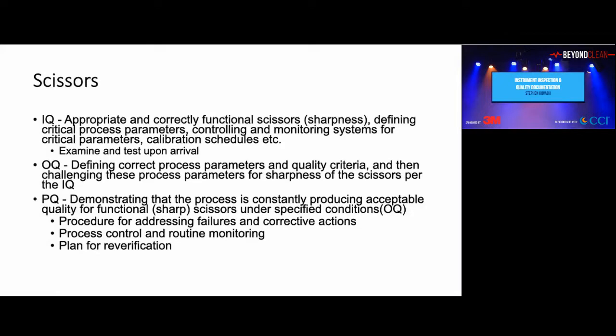You're going to look at it, make sure there's no burrs and blades, check it. But again, that IFU says you inspect it, you send it through the washer, manually keying. That's when you're going to check it again, and you're going to accept it or not. So you'll define what criteria. Maybe as the IFU that I showed you, it says you got to go through gauze. But if you have a policy that says you're going to use some non-latex material, you back it up with the right footnotes that instead of using gauze, you're going to use whatever, blue, green, red to test it.